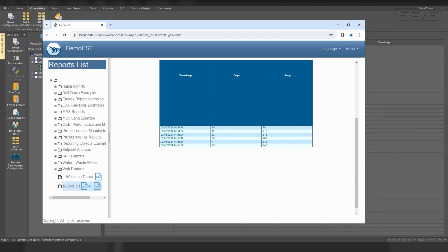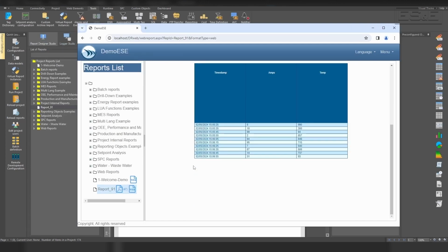So let's turn normalizing off now. If we go to this report, we'll see that it's every 10 seconds: 25, 35, 45, 55, 05, 15, 25. So it's still logging every 10 seconds, but it's not doing it at an interval in relation to the top of the minute. In other words, it's not hitting 0, 10 seconds, 20 seconds. So that's what normalization does for us.